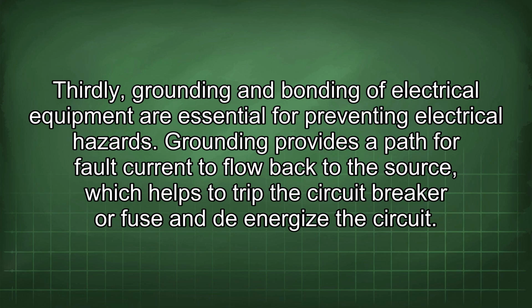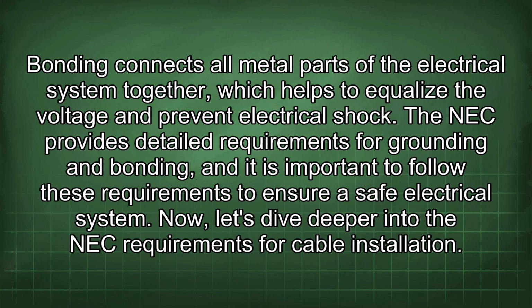Thirdly, grounding and bonding of electrical equipment are essential for preventing electrical hazards. Grounding provides a path for fault current to flow back to the source, which helps to trip the circuit breaker or fuse and de-energize the circuit. Bonding connects all metal parts of the electrical system together, which helps to equalize the voltage and prevent electrical shock. The NEC provides detailed requirements for grounding and bonding, and it is important to follow these requirements to ensure a safe electrical system. Now let's dive deeper into the NEC requirements for cable installation.